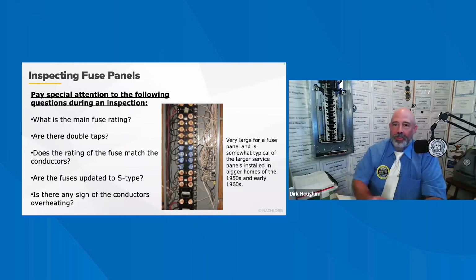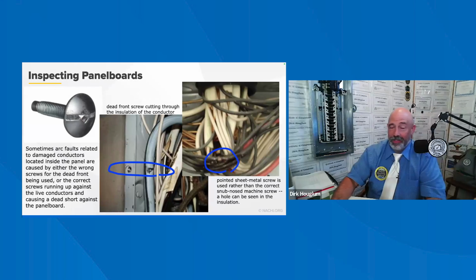So there are two major problems with inspecting older fuse panels. First, to check the main fused amperage, the blocks have to be pulled out, which shuts off the power to the entire house. The second issue is that these panels tend to be unsuitable for modern high amperage demands. They also tend to exhibit double taps and overfusing quite a bit. So the dead front cover screws are very important to check. And like I said before, they have to have the blunt end, because I've had it where I've unscrewed one and blew a fuse panel because obviously the screw had damaged the wire.